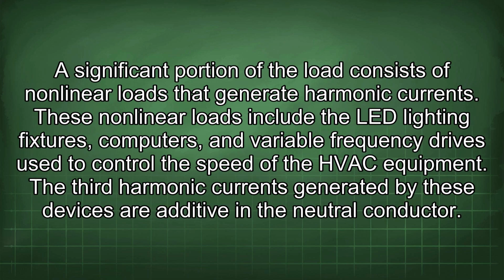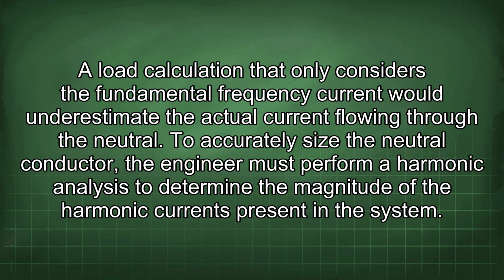A significant portion of the load consists of nonlinear loads that generate harmonic currents. These nonlinear loads include the LED lighting fixtures, computers, and variable frequency drives used to control the speed of the HVAC equipment. The third harmonic currents generated by these devices are additive in the neutral conductor. A load calculation that only considers the fundamental frequency current would underestimate the actual current flowing through the neutral.